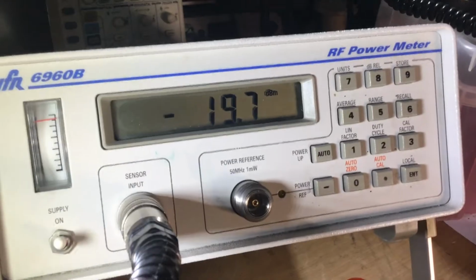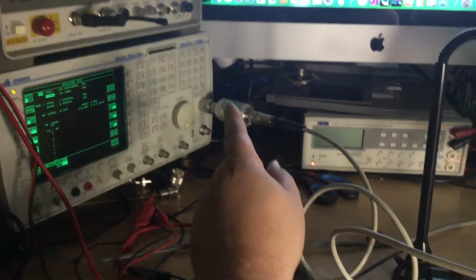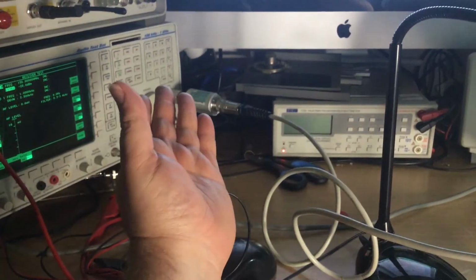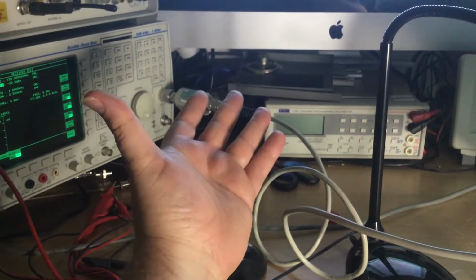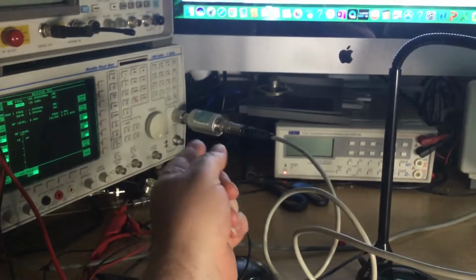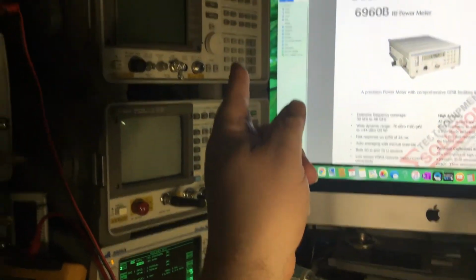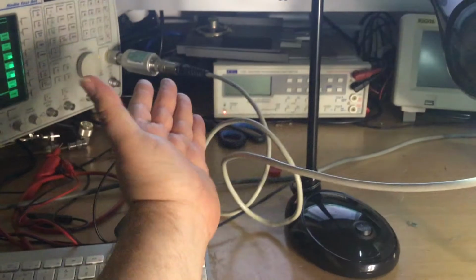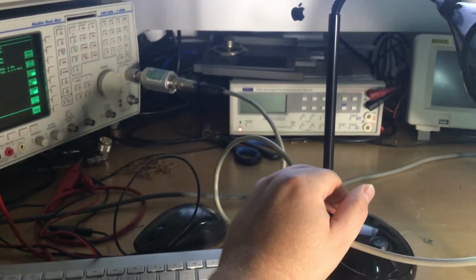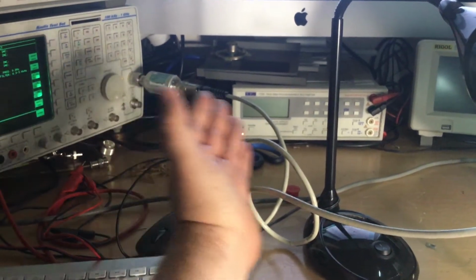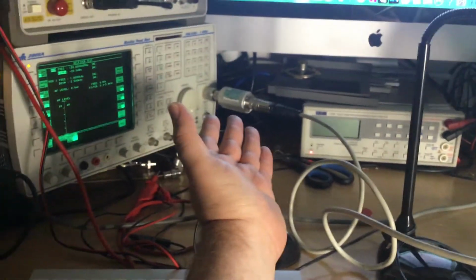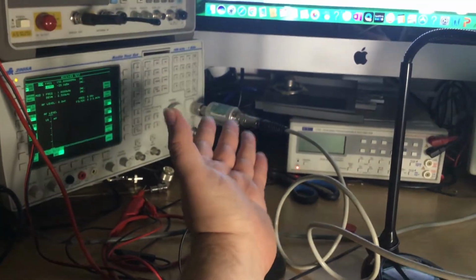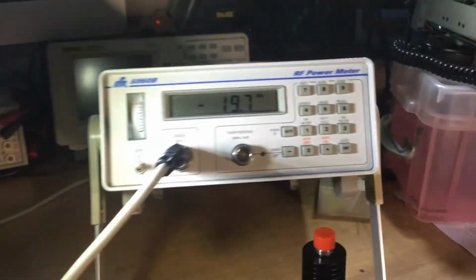So that signal generator is, you know, spot on. It's -20 dBm, and that's the application that you'd use it in as well, because you're measuring the signal directly at the source, whereas if you're using RF cables, like with a spectrum analyzer for example, you'd have an RF cable connecting from the SIGGEN up to the spectrum analyzer, then you would simply introduce more losses, because obviously the cable has loss. So this is a method of measuring a signal directly without having any losses to cater for in cables.